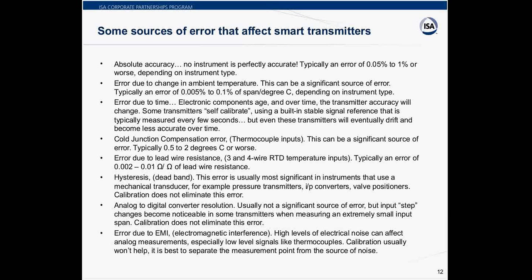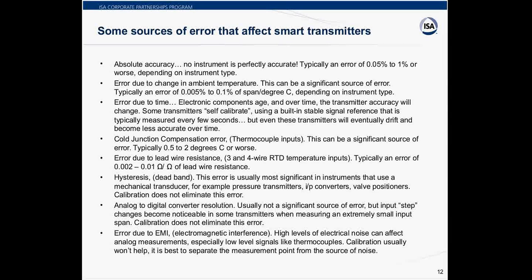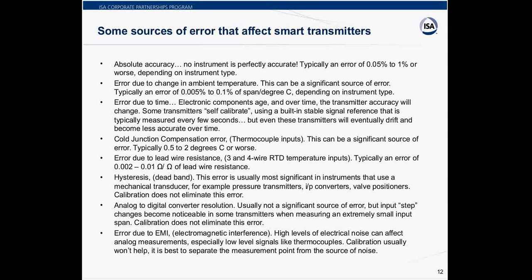Over time, transmitters — including smart transmitters — are going to lose accuracy due to the aging of components and transducers inside them. You can calibrate the transmitter, which will usually bring it back to factory accuracy. How often the transmitter requires calibration is hard to say — it's usually determined on-site empirically. If the calibration team checks the transmitter every six months and finds that it's still within spec, then after a certain number of checks they might increase the interval to, say, one year.